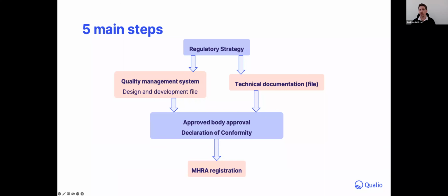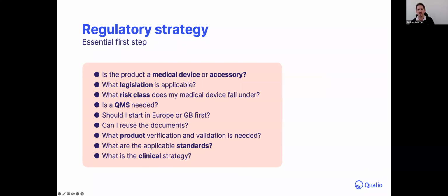As a first step, the regulatory strategy isn't technically required by the UK MDR, but it really is essential in order to ensure that the route to compliance is simple, cost-effective, and as risk-free as possible. From our perspective, for all new product developments that we work on, we'd strongly recommend a regulatory strategy be produced pretty much every time. And pretty much every time we've done one, we've been able to make sure that the faster or cheaper route has been taken to get to market. Generally, a regulatory strategy would cover the things that are listed here.